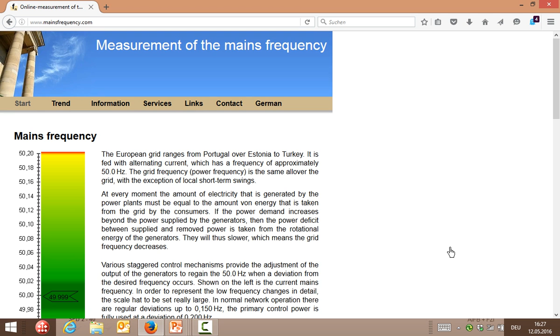We have primary control. Primary control is directly controlled by frequency, so it's used in a proportional way. That means the higher the deviation from 50 Hertz is, the more energy has to be used in order to balance it out. The more primary control energy has to be used. It can be activated within 30 seconds and is used for a potential duration of at least 15 minutes.